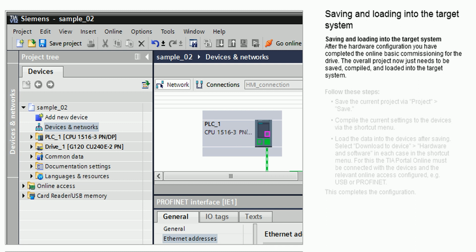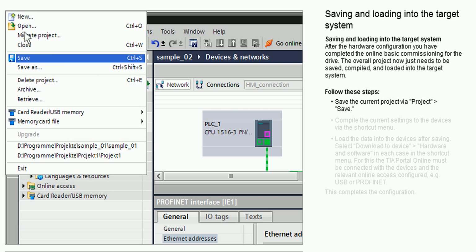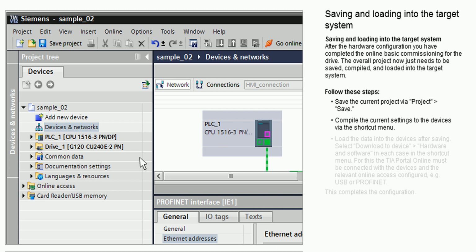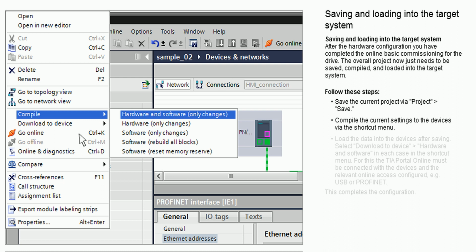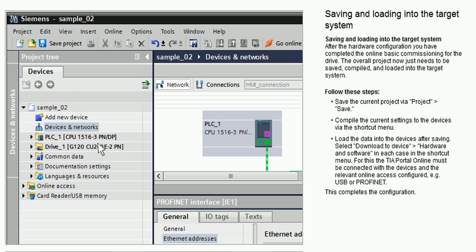Saving and loading into the target system. After the hardware configuration, you have completed the online basic commissioning for the drive. The overall project now just needs to be saved, compiled, and loaded into the target system. Follow these steps. Save the current project via Project, then Save. Compile the current settings to the devices via the shortcut menu. Load the data into the devices after saving.